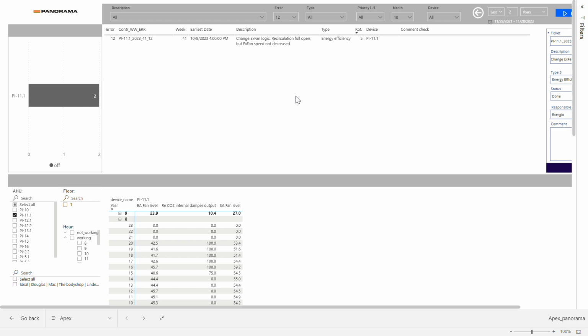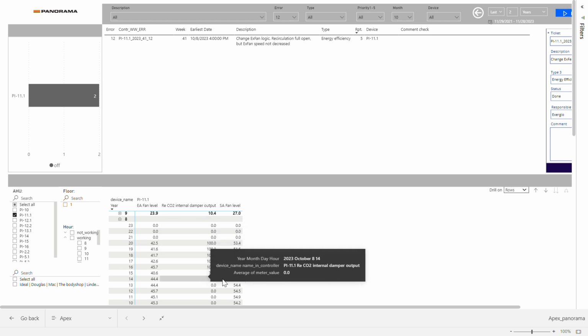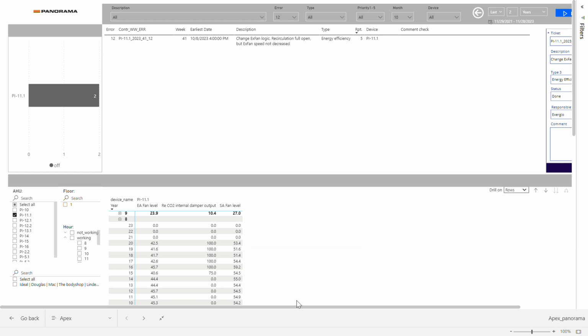about algorithm. We can see a change in fan logic - something is wrong with the fan logic, and it's very funny, we find it in many cases. Someone programmed 10 years ago the logic of the unit, and if the CO2 level is good enough, they use the same air to recirculate inside.